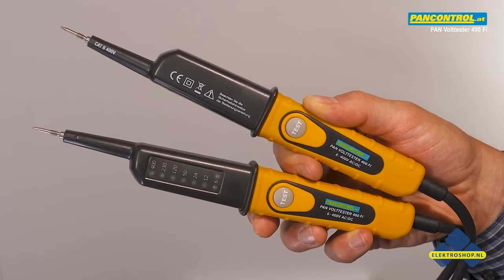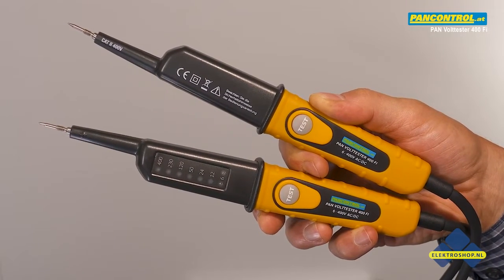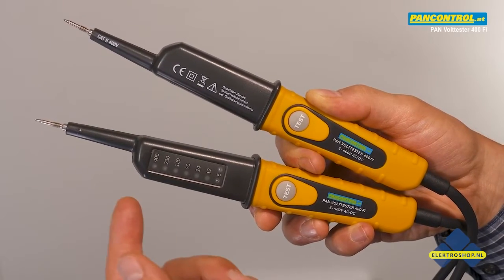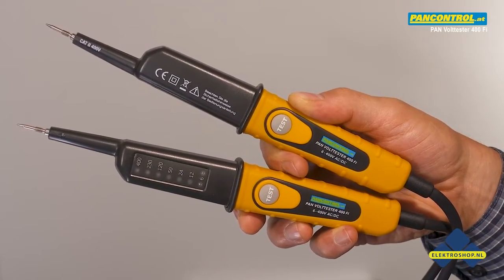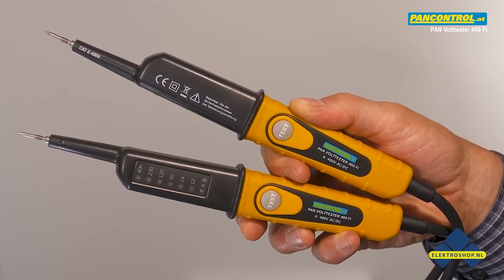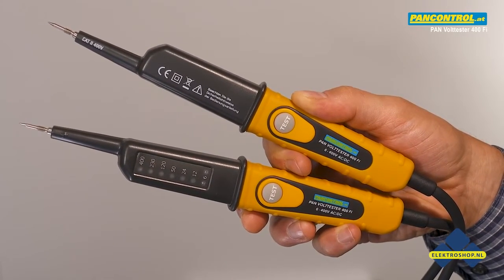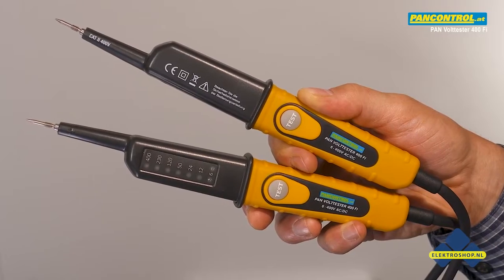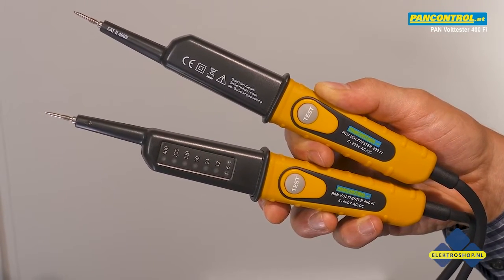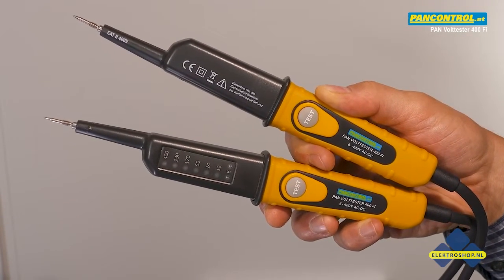The PanControl Pan Volt Tester 400Fi is a two-pole voltage tester for AC and DC voltage from 6 to 400 volts, with polarity indication for DC. Pressing the two test buttons increases the current to 30mA at 230V to check the proper earth connection of the socket, the function of the RCD switch, and to suppress ghost voltage.